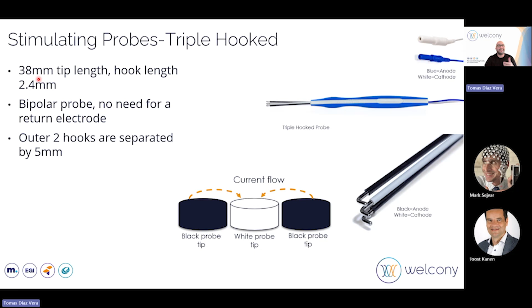If you want to use the triple hook as a stimulator, you need to be mindful that the black shaft is the anode as long as you connect the blue wire into the anode port, or the positive port, of the output in the IONM machine. We have this iteration of 90 degree triple and double hook in 38 millimeters, but we are launching right now, releasing, an extended shaft. So it's a longer probe, double and triple hook.